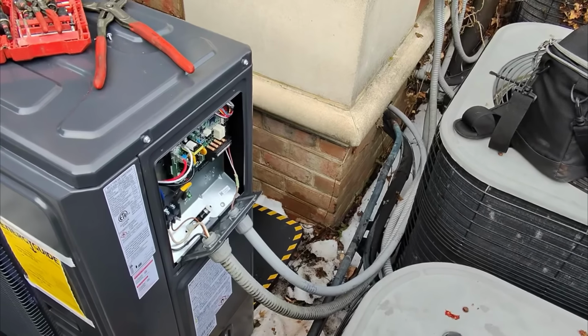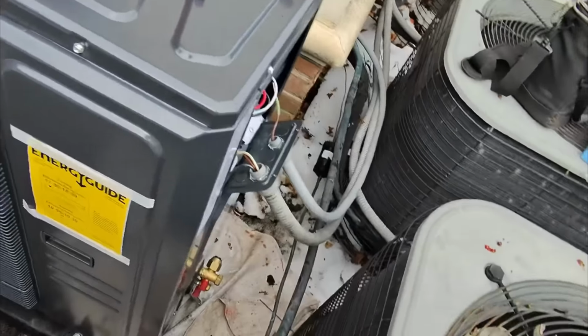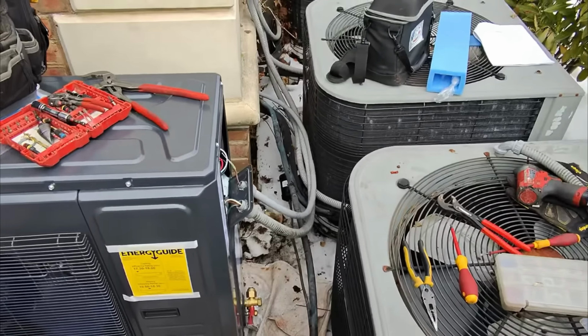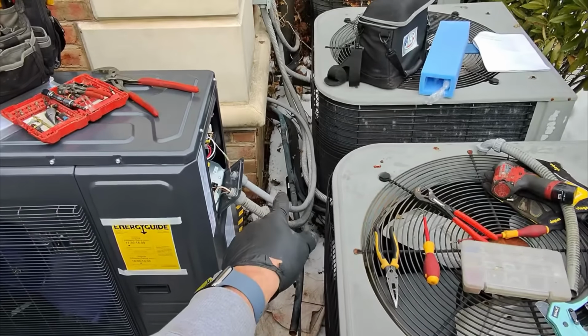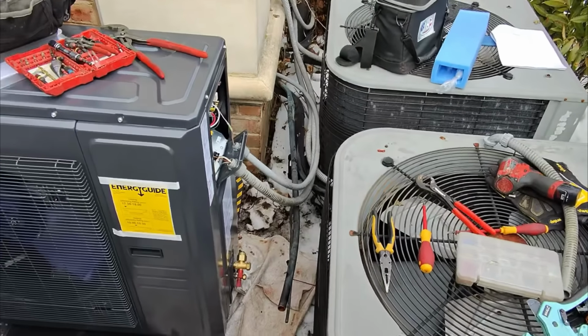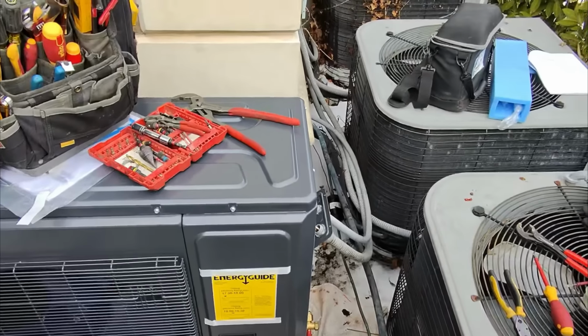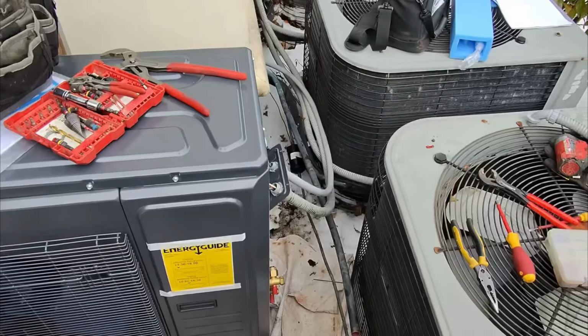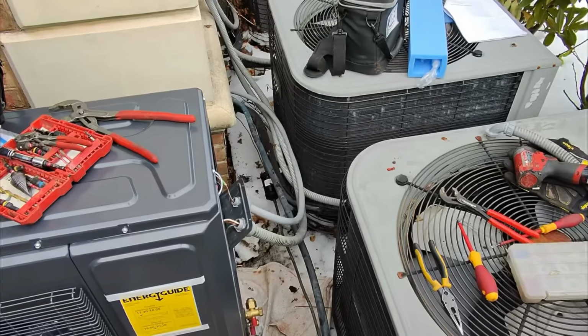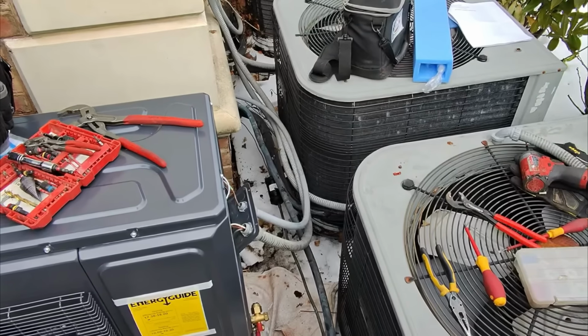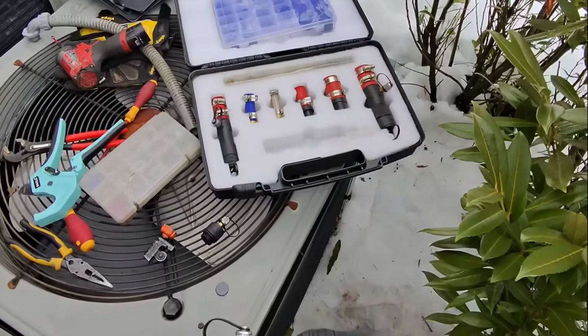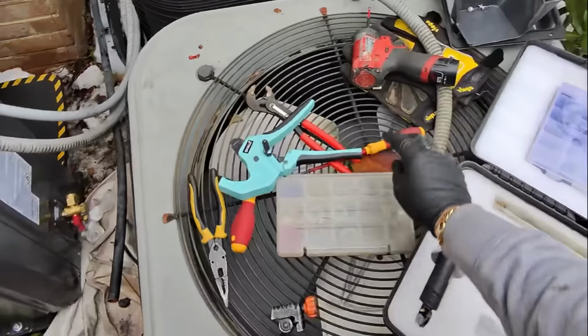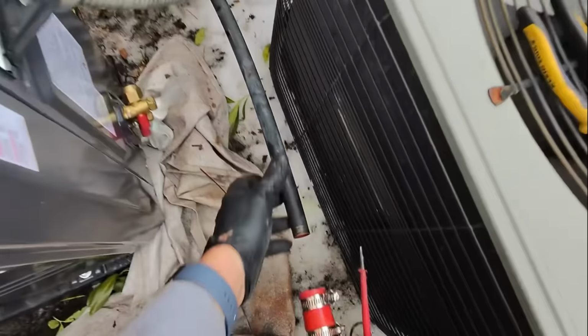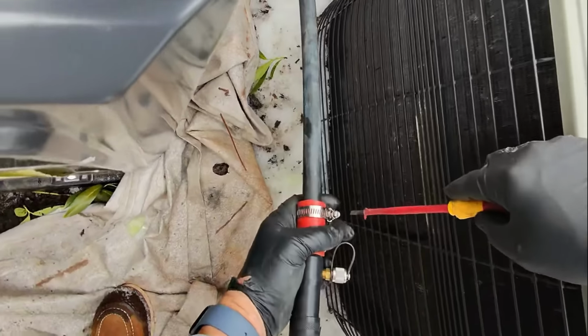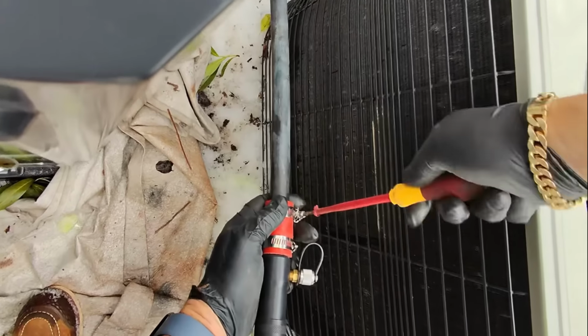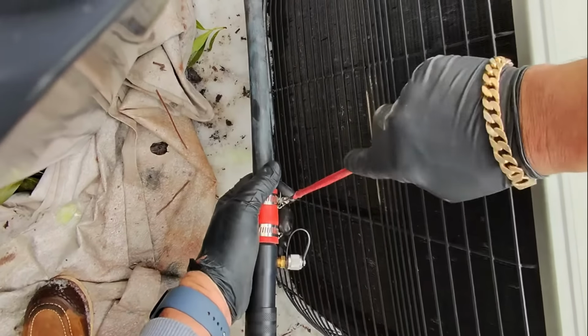Now the fun part. We have to line wipe or pipe wipe with the pipe wiper the existing 7/8 and 3/8 line set. Before we do that, I'm going to cut out the filter dryer that's back there and bring Daniel up the nitrogen and the pipe wiper. All right, here's the pipe wiper system. I'm going to secure it onto the pipe. Tightening up the hose clamps.